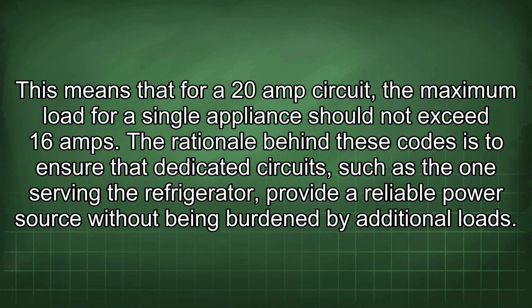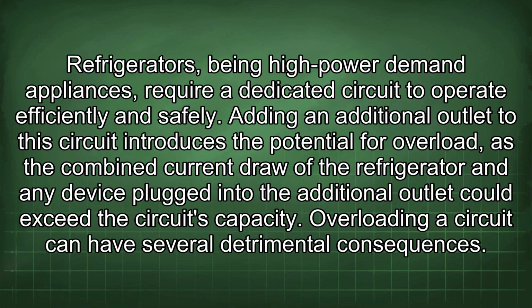The rationale behind these codes is to ensure that dedicated circuits, such as the one serving the refrigerator, provide a reliable power source without being burdened by additional loads. Refrigerators, being high power demand appliances, require a dedicated circuit to operate efficiently and safely. Adding an additional outlet to the circuit introduces the potential for overload, as the combined current draw of the refrigerator and any device plugged into the additional outlet could exceed the circuit's capacity.